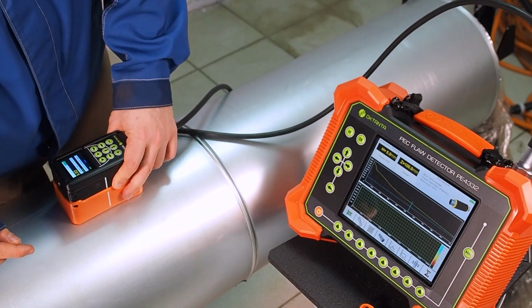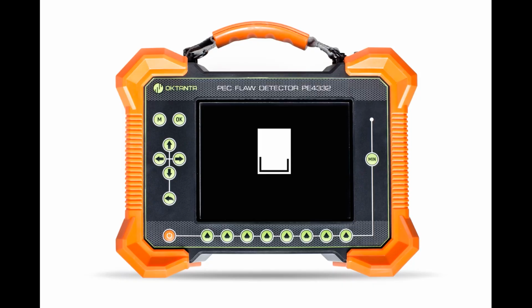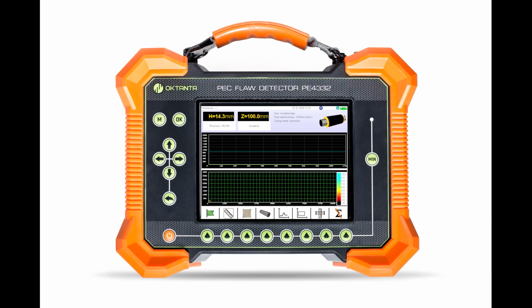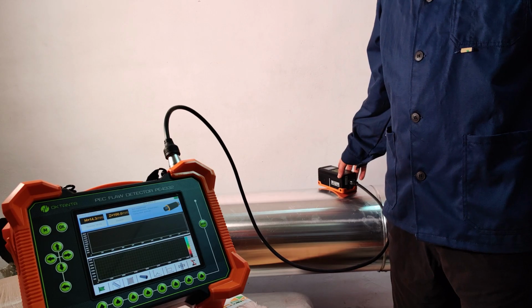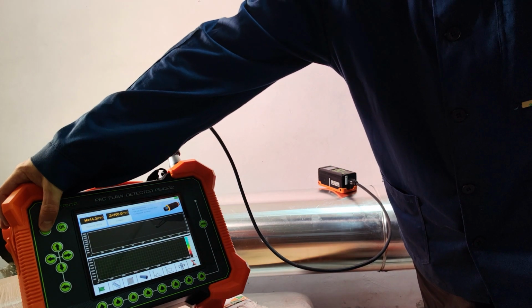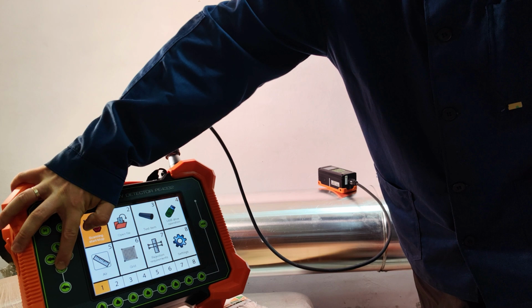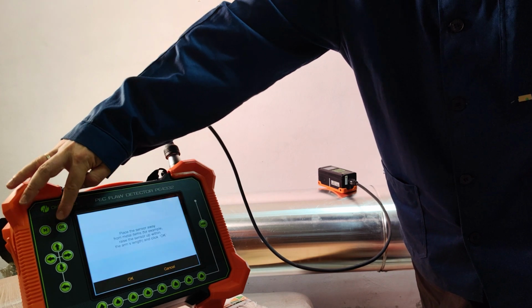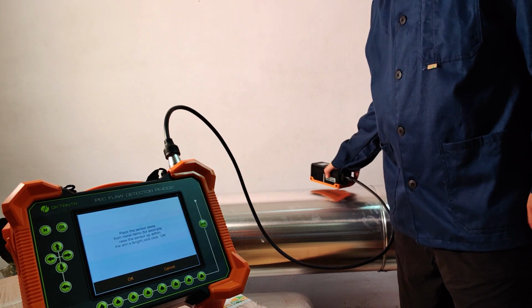Today, we will study in detail the procedure of flaw detector PE4332 calibration as well as the beginning of measuring a test object. First, we will calibrate a sensor. The sensor has a strong magnetic field, so we will take it away from all metal objects, for example, by raising it by more than half a meter above a pipe.